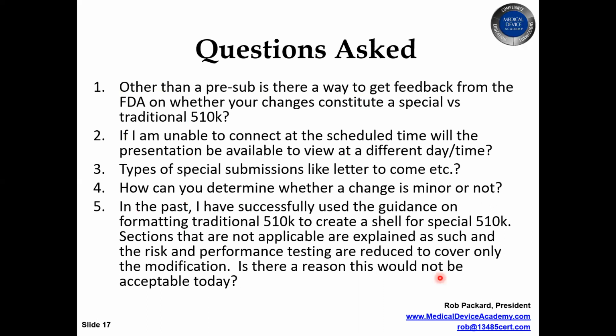Next question. How can you determine whether a change is minor or not? Well, the FDA goes through the trouble of creating these guidance documents to explain what is a minor modification, what is a major modification. Anything that is going to involve multiple functions in the FDA to review your submission, that's not going to be a minor modification. If you're changing the indication for use or the intended use, that's not a minor modification. If you have clinical data, not a minor modification.